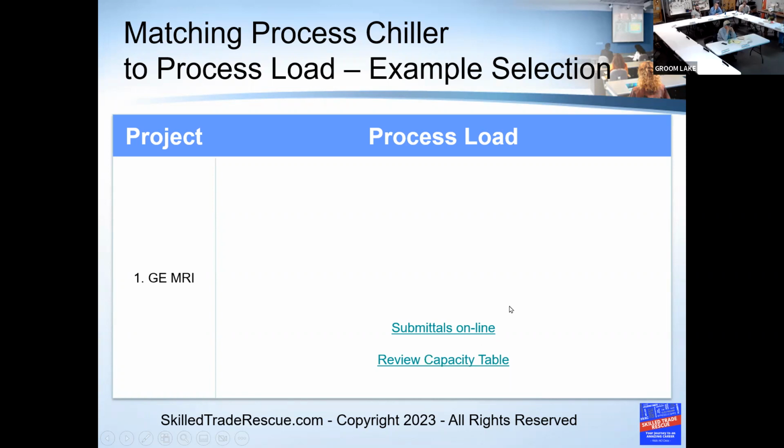Yes, sir. Can you please define approach the way you were using it? Yeah, I know I've got some refrigeration guys. So the approach in process chiller world is the fluid of the cooling medium as it's entering whatever we're cooling. Now, I do know there's also a term in refrigeration that's similar. And yeah, that's the way it was taught to me. There's evaporator approach, condenser approach.